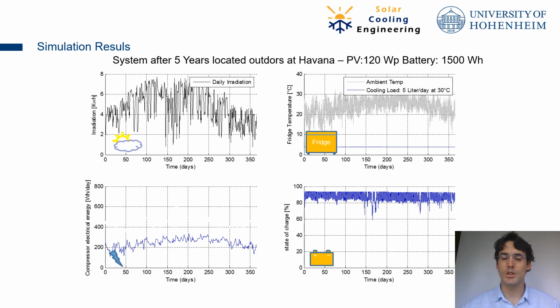The refrigerator is connected to a solar system with 120 watt peak and a battery of 1500 watt hour. This was the optimization we did for this location, for a refrigerator that has to cool down 5 liters of water per day from 30 degrees to the set point temperature of 4 degrees.